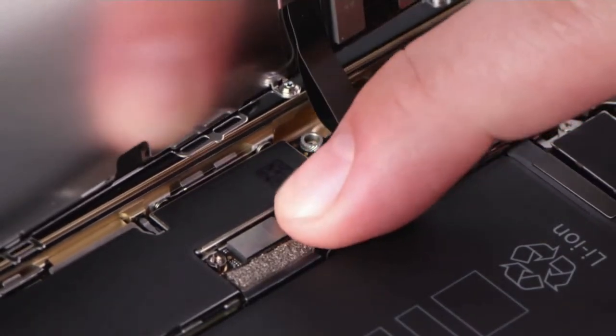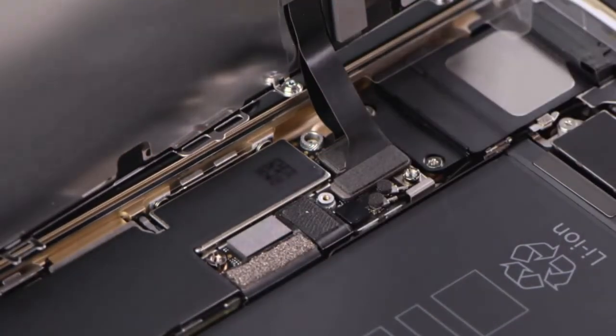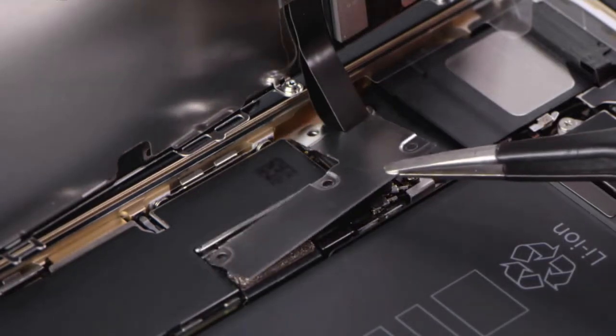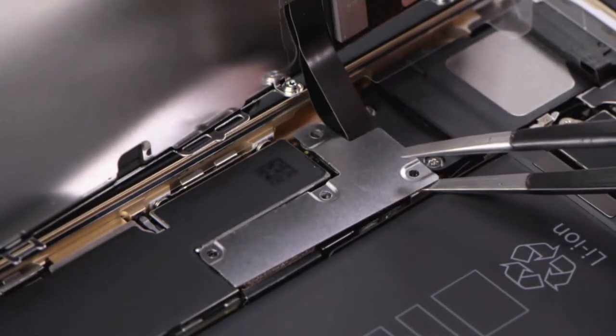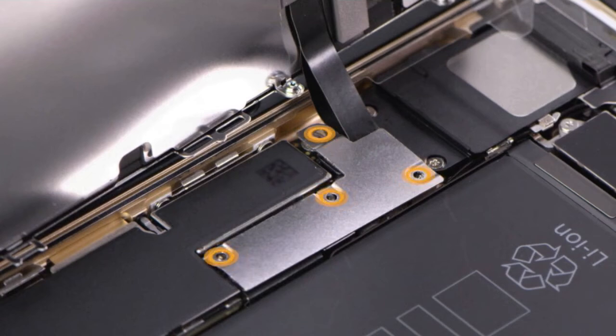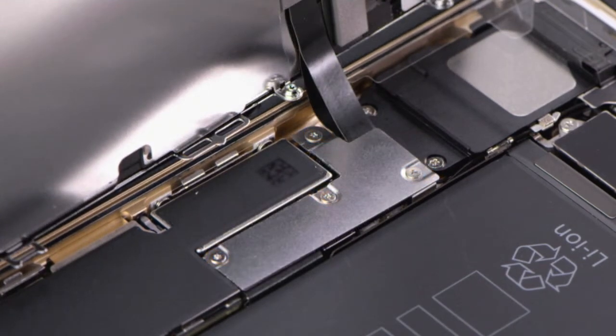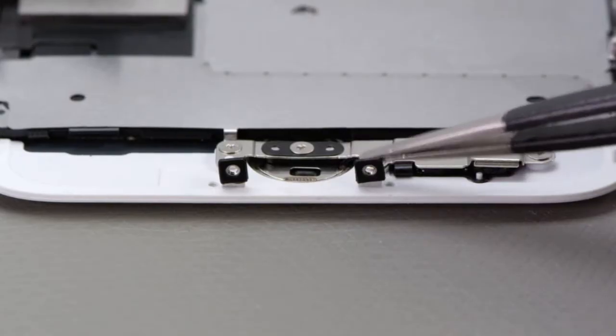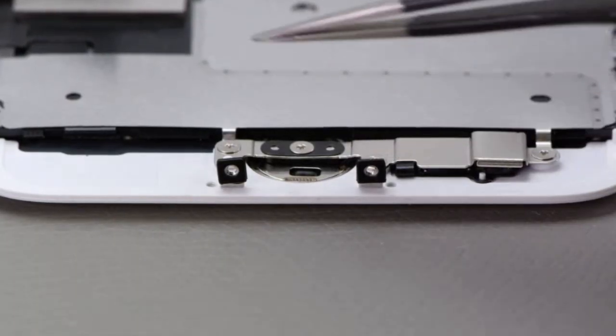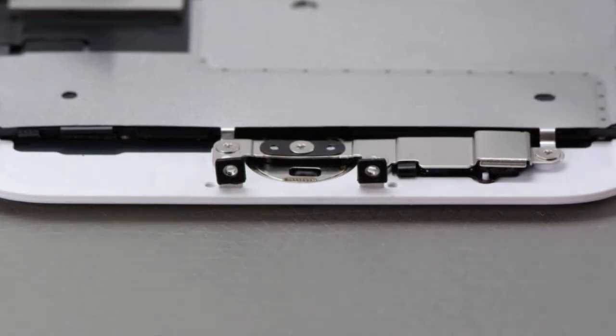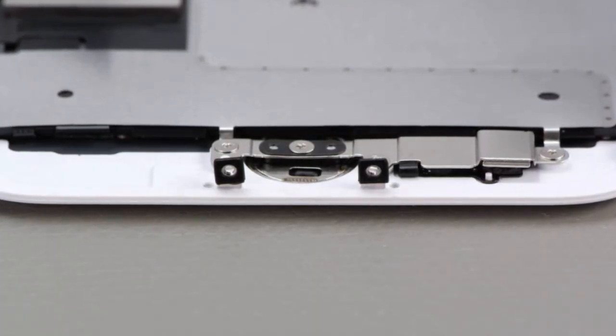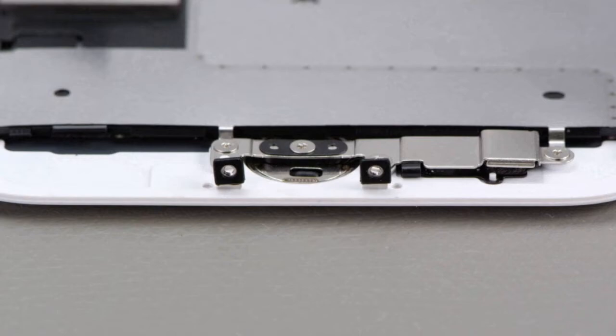Connect the battery to the logic board. Install the battery display cowling. Use the black torque driver and the microsticks bit to install 4 new tri-lobe screws. Check that the gaskets on the screw bosses are in position. Adjust them if necessary. If the gaskets are missing or damaged, replace them with new ones.